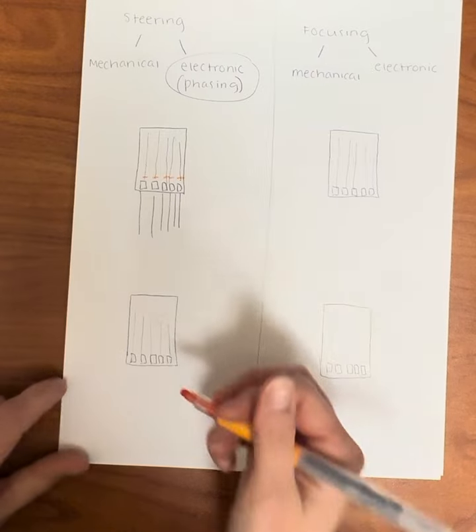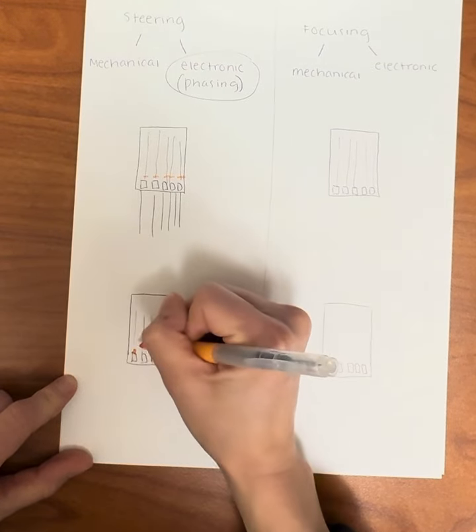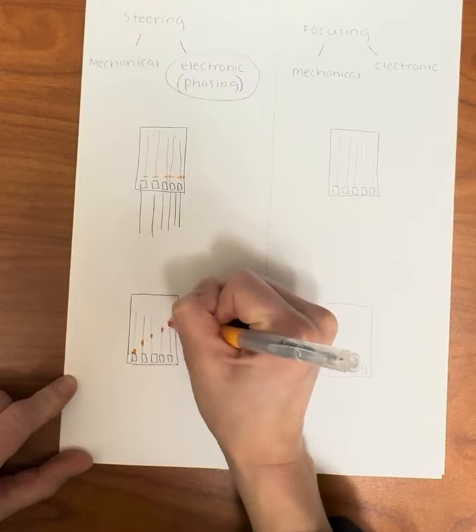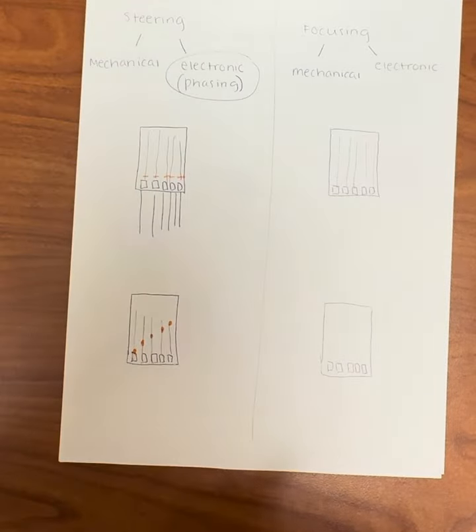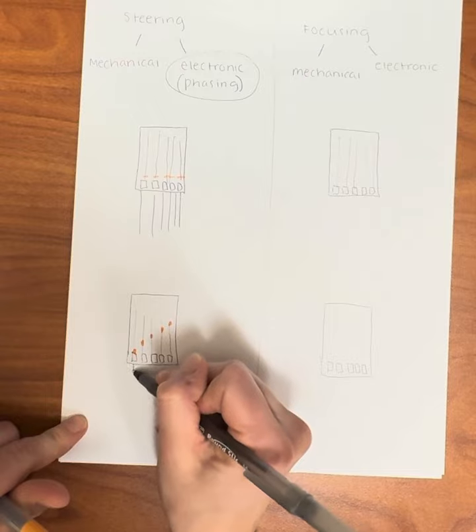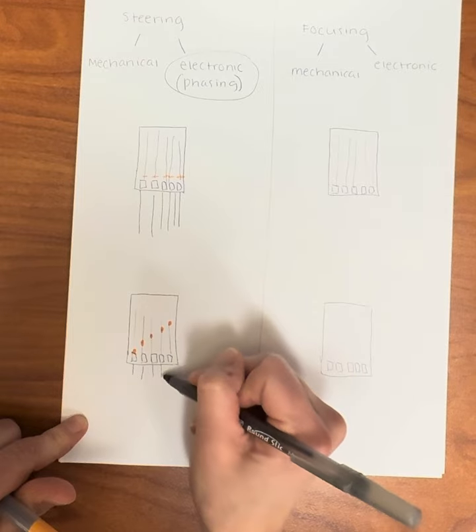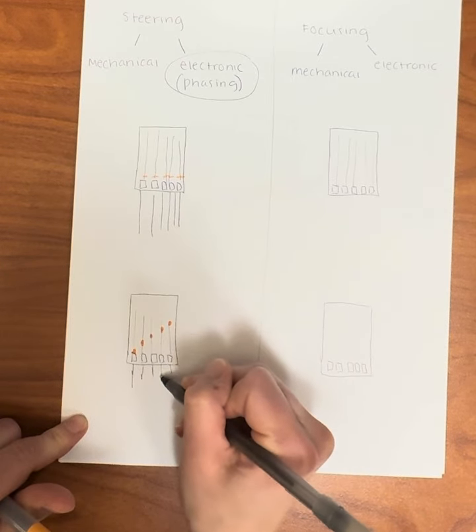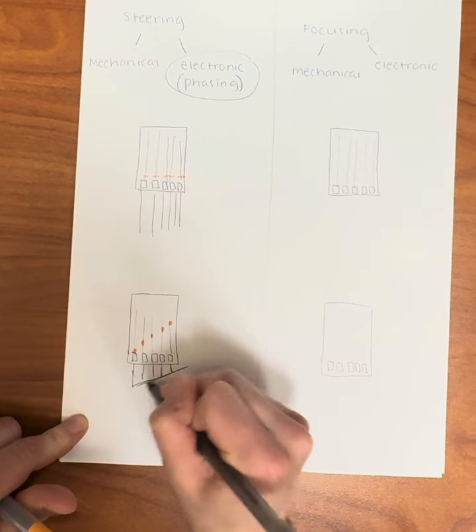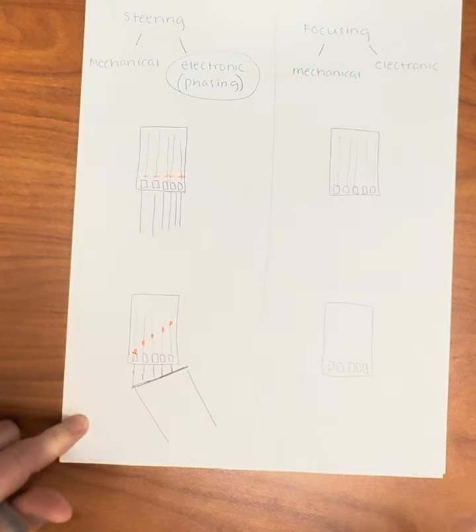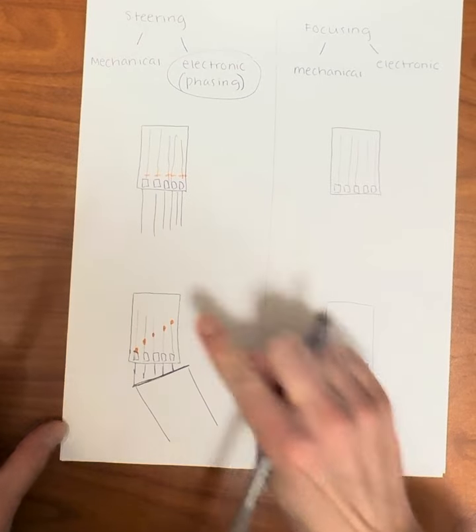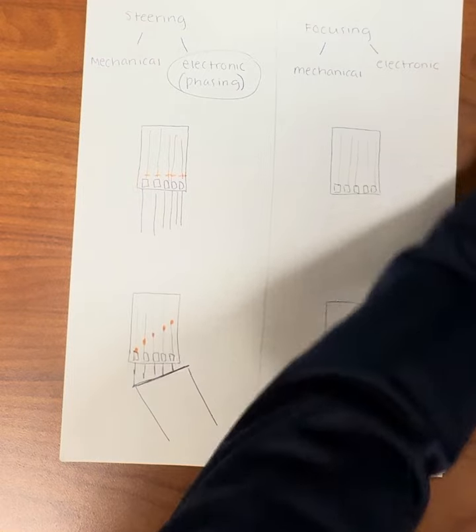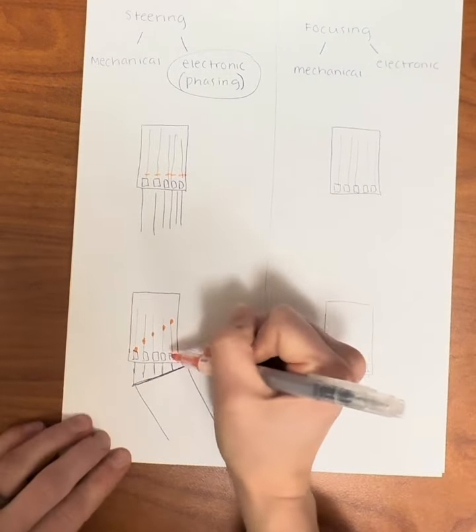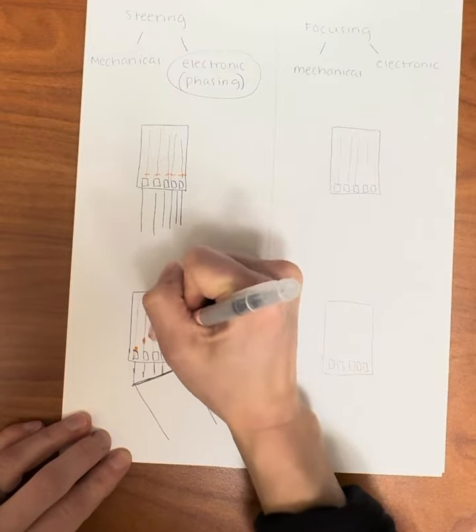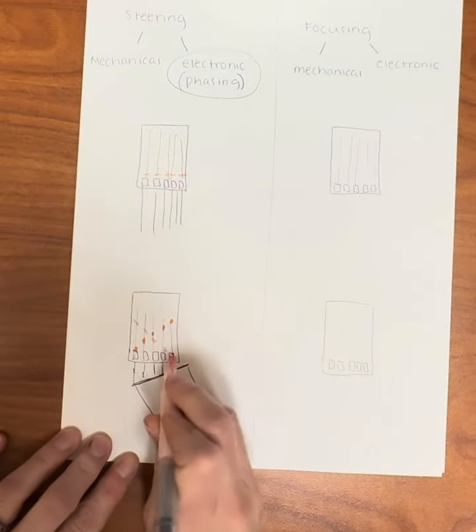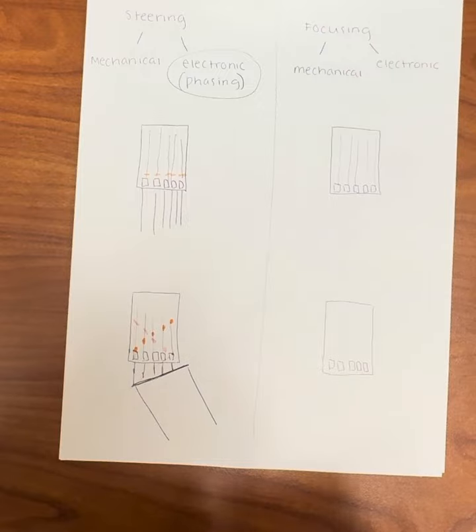So if we zapped this element, then this one, then that one, then that one, then that one, this is representative of the time delay. And so what would happen is that this one would go first, then this one, then that one, then that one, then that one. And because of the way that they were delayed, the wave front will actually come out and bend in the same direction of the delay. So if we were to delay these in the opposite direction and zap over here first, and then here, and then here, and then here, and then here, our wave front would go in that direction out of the transducer.